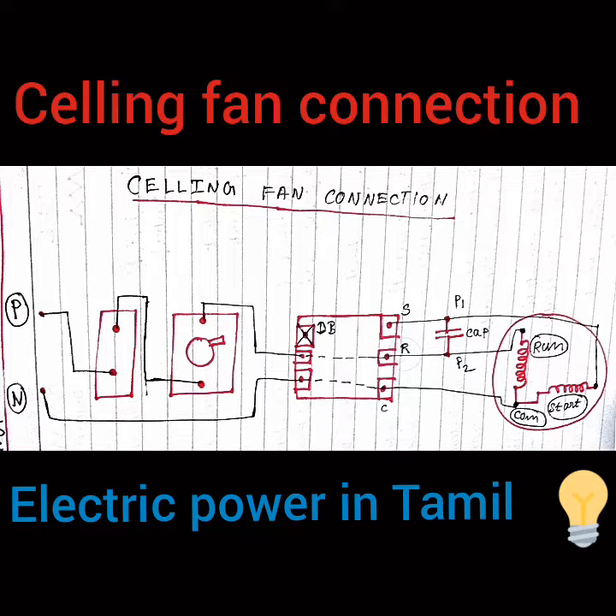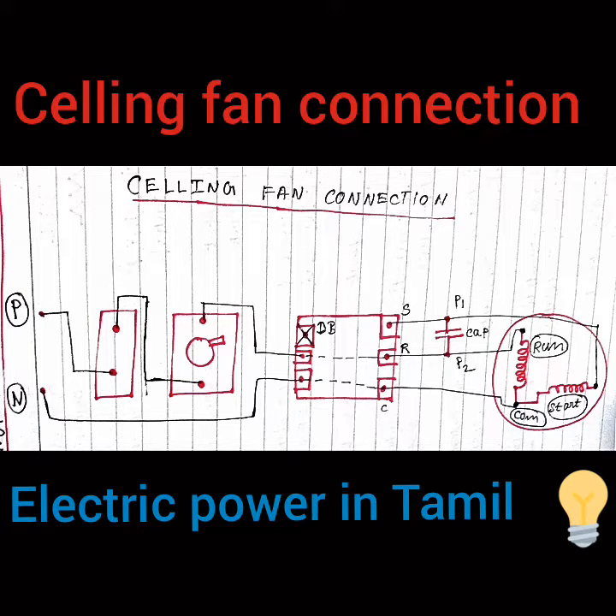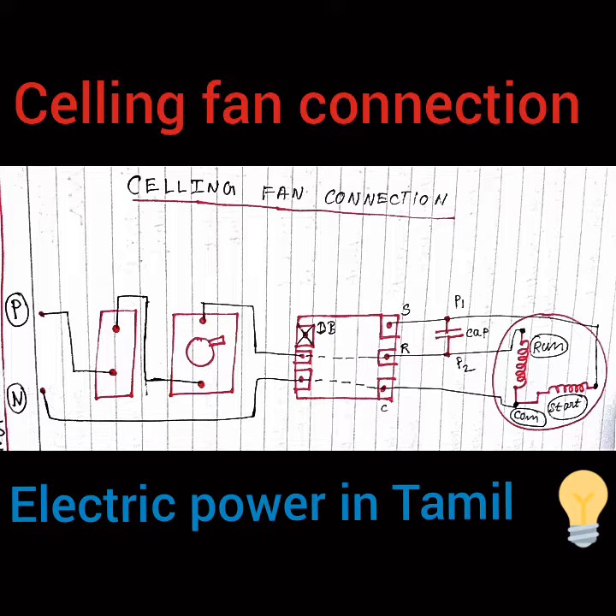If you look at the center side, there is a joint here. The common point and the second line connect together. The starting terminal connects to the center. The important thing is that the phase goes to the starting winding. The capacitor connects between the starting terminal and the running terminal.